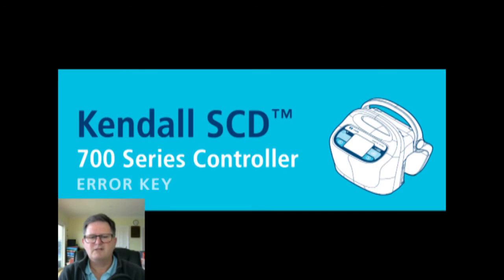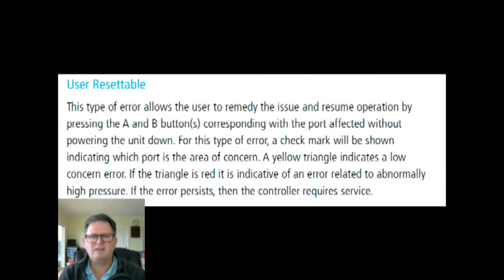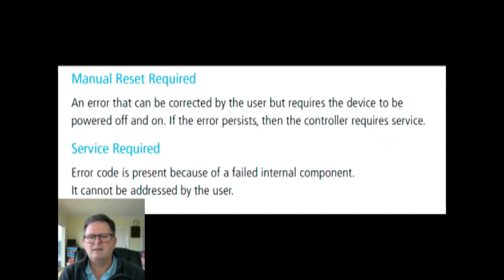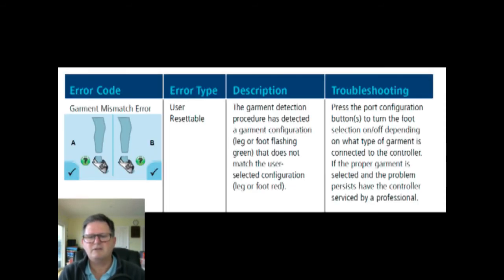But there's quite a few error codes. There's a separate manual that explains all of these quite well. I'm not going to go through all of them, but there are 3 basic types: one you just acknowledge and keep going, which they call user resettable; one where you have to turn the unit off and on and restart it, which they call a manual reset; and one that's service required, where you have to send the unit away to get fixed. I've just picked these out from the manual.